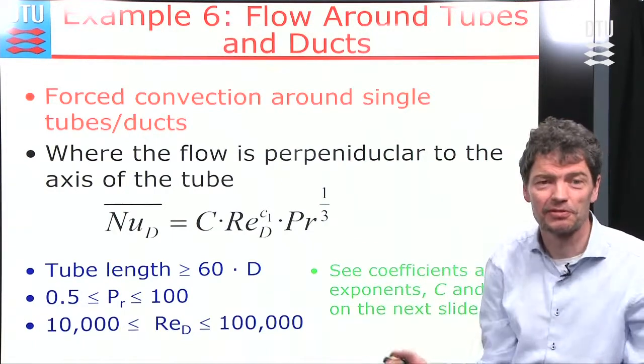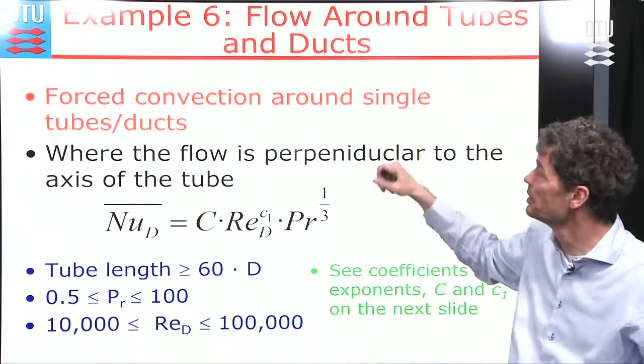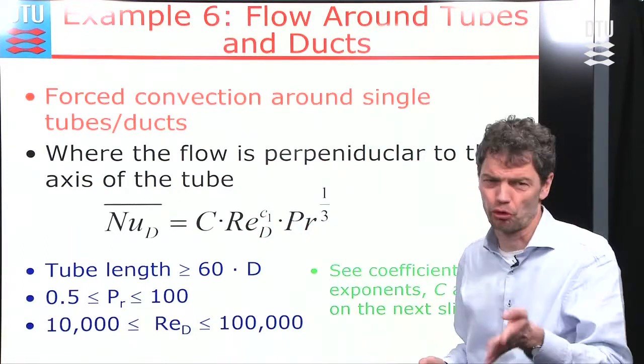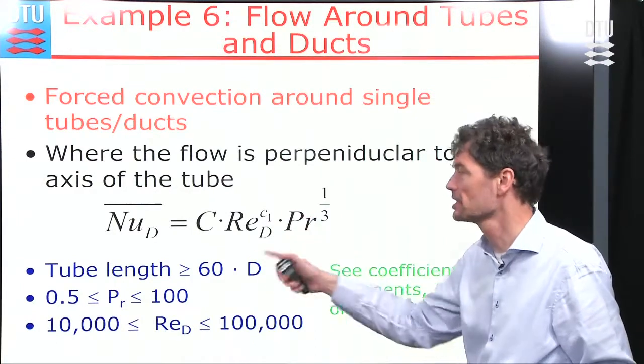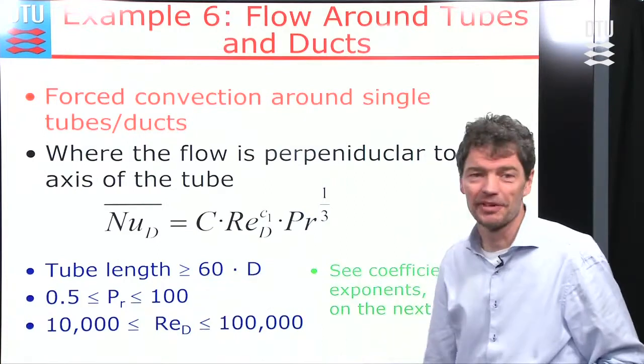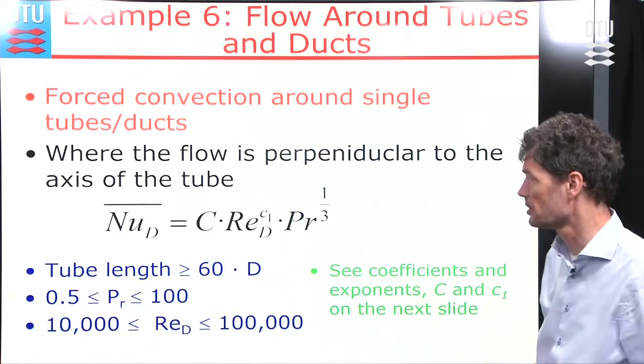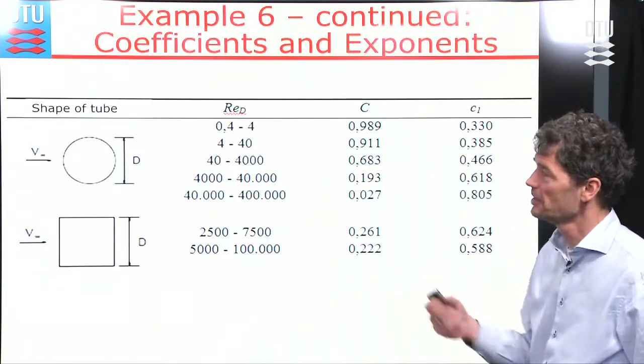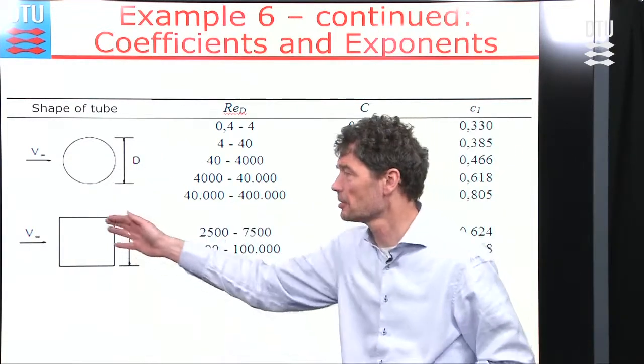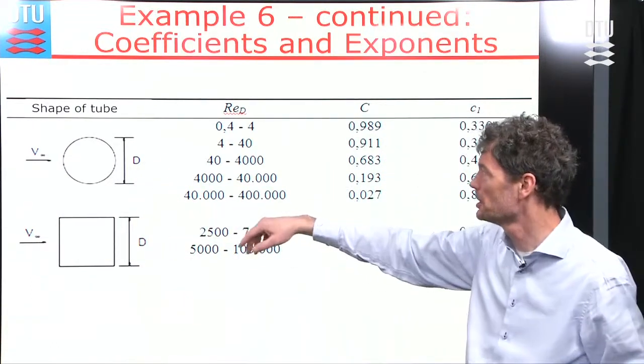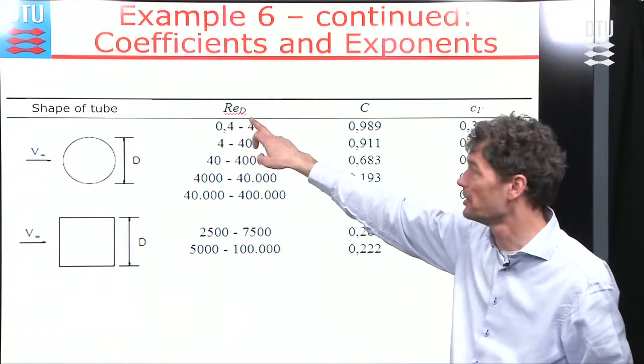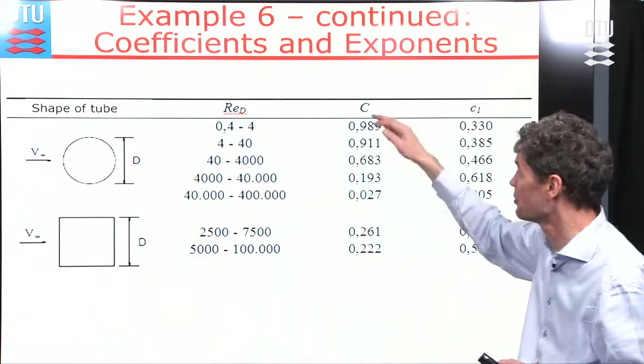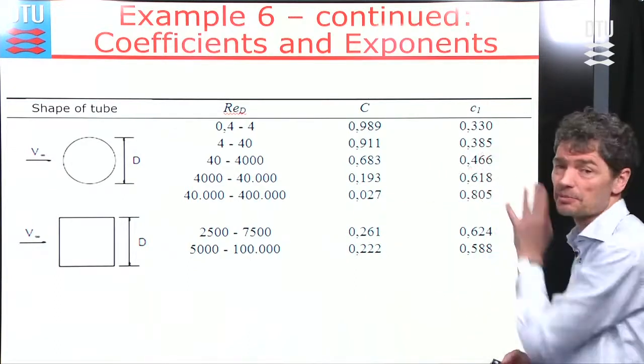Example six covers forced convection flow around a tube or duct. A formula similar to previous ones uses the Reynolds number and Prandtl number raised to powers with a coefficient, with ranges of validity. The coefficients and exponents are found in a table on the next slide, depending on whether the geometry is circular or rectangular. The diameter serves as the characteristic length for calculating the Reynolds number.